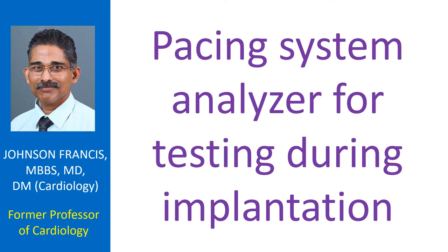Modern pacing system analyzers have the capability of dual chamber AV sequential pacing. The PSA can display real-time intracardiac electrogram sensed from the pacing lead as well as surface ECG if surface ECG leads of the analyzer are also connected.